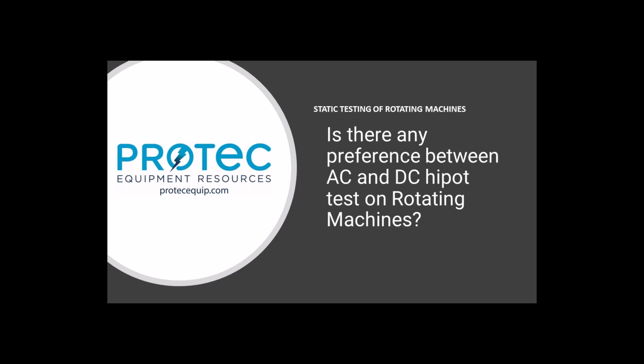Really, the only place where AC comes into play that I'm familiar with is when we do partial discharge testing. Power factor testing is done at AC, and SFRA is actually done with injected AC signals. But for most of the basic static tests, DC still rules.